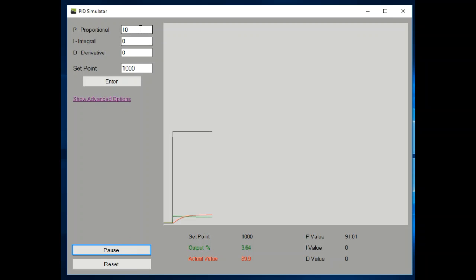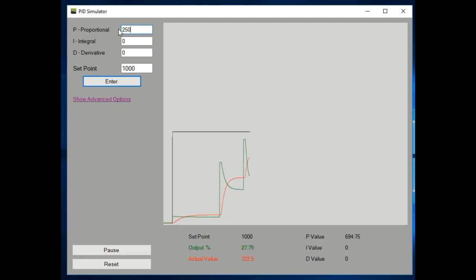Now let's bring this proportional up. The idea when setting up the proportional value is to keep increasing and increasing the value until your controller becomes unstable. By unstable, I mean it goes into oscillations and the oscillations become larger and larger. If the oscillations become smaller and smaller, the controller is stable. We want the breakpoint between the two, so let's find that.